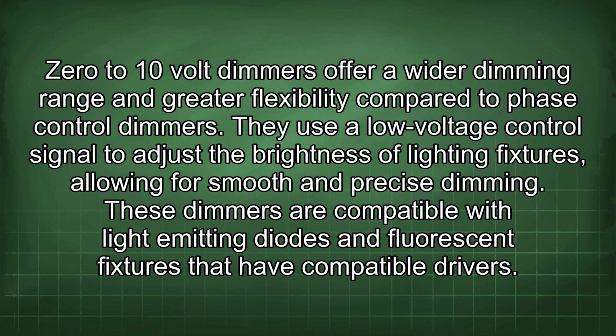0 to 10 volt dimmers offer a wider dimming range and greater flexibility compared to phase control dimmers. They use a low voltage control signal to adjust the brightness of lighting fixtures, allowing for smooth and precise dimming. These dimmers are compatible with light-emitting diodes and fluorescent fixtures that have compatible drivers.